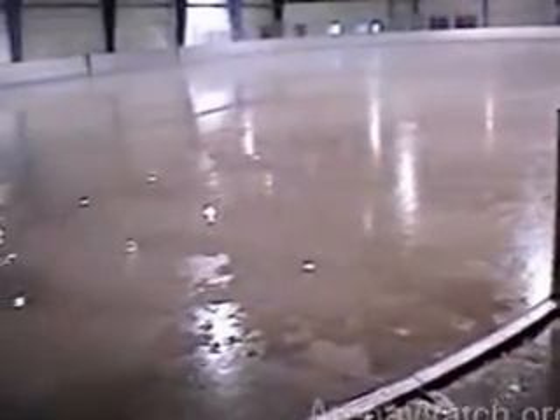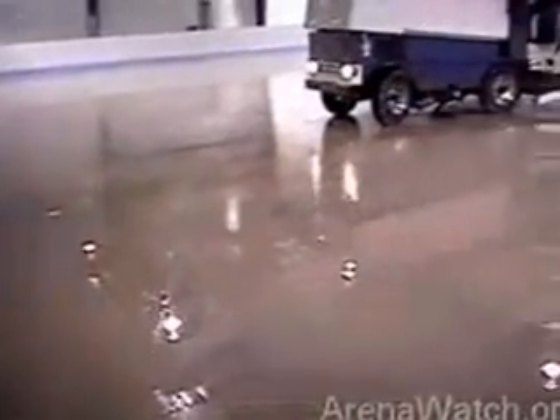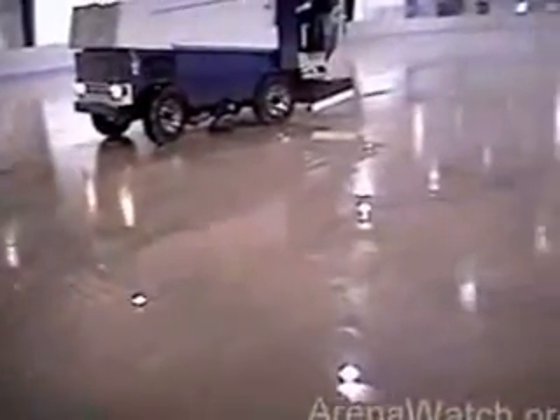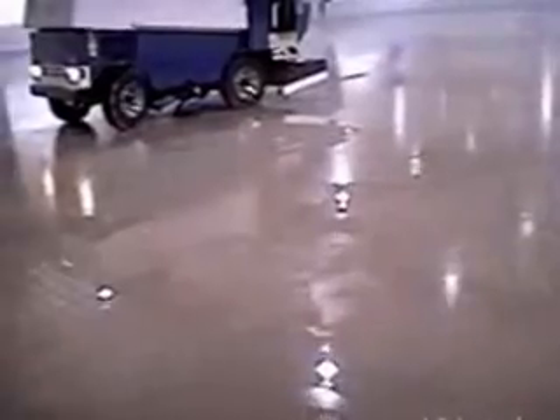At this point, the ice sheet's been flooded to a level condition, just prior to the painting process. We take the ice resurfacing machine out and drive it around to relieve all the stresses created during the first freezing process. What we want to do is create a condition where the ice will crack before we paint it and settle in, so it doesn't crack after the painting process, which would create an unsightly condition and ruin the paint job.